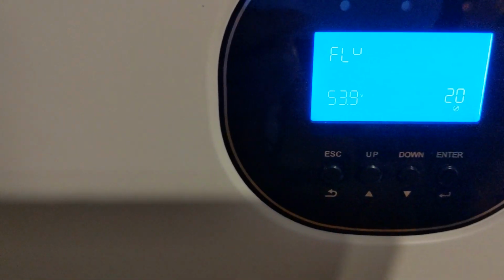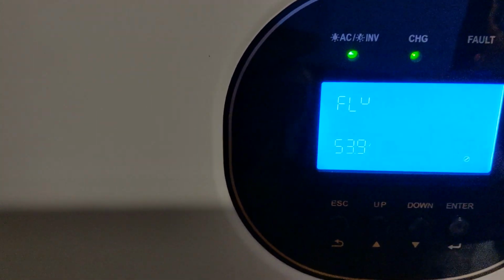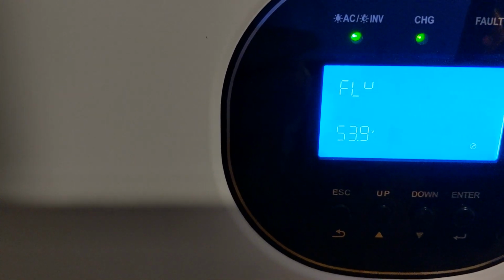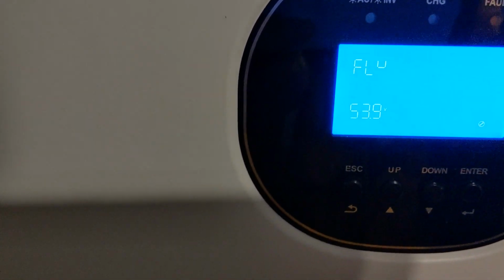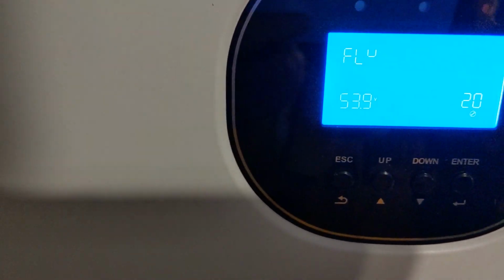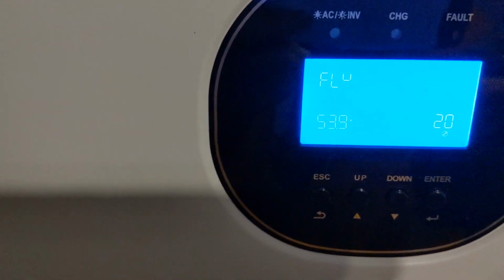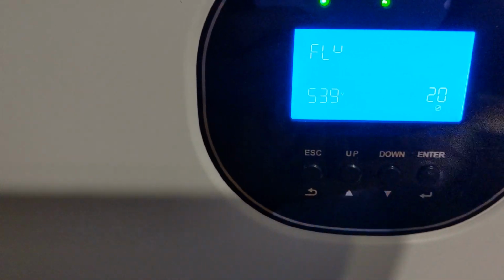The next setting is the float charge. I have mine set at 53.9, so it basically gets it up to that 54.1, and then it dials back into this float arrangement, keeping the batteries floated at that level.